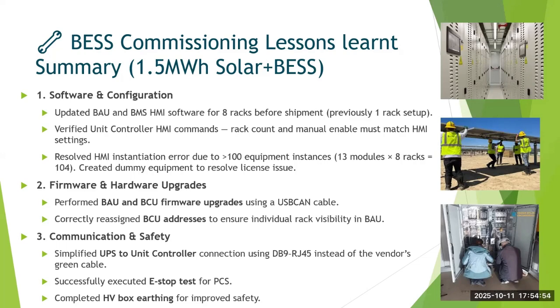The other one was with respect to communication. A UPS was there to power the auxiliary power, because even the controller we use to control it should have UPS power, so that in case the grid goes off and the batteries are at 5% SOC, you can ensure this is taken care of. For the UPS to our unit controller, we used to have a serial to RJ45 connection. So again, we came up with connecting directly to RS485. There we reduced the additional cable which was required.